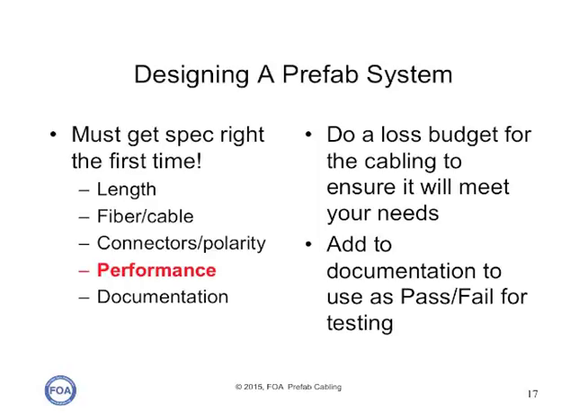You need to specify the performance of the cable plant. You need to do a loss budget for the cabling to ensure it will meet your needs. MPO connectors have higher loss, generally speaking, than single fiber connectors, so you don't have the option of using lots of interconnects. You've got to do a loss budget, check it against the systems you plan on running on it, and add all that to the documentation. And by the way, make sure that you and your vendor agree on how you're going to test the performance of the cable plant, because that is very important to make sure that you know what you're going to get and can test it and prove it when it's delivered on site.